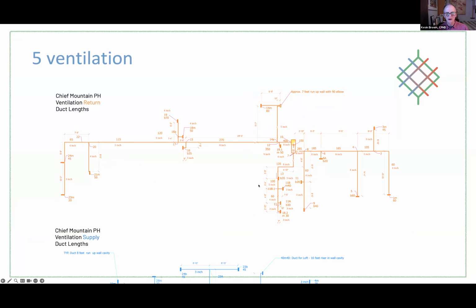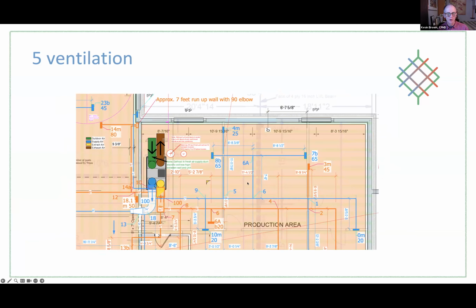Once I'd done that, I did some plots for a mechanical engineer who could go over all the static pressure losses, so we did plots for the exhaust as well as the supply duct lengths, then overlaid that on an accurate plan with the truss layout ghosted in the background. That wasn't an accurate drawing of the open web truss I showed you before, but we did have accurate data from the shop drawings of the truss system.